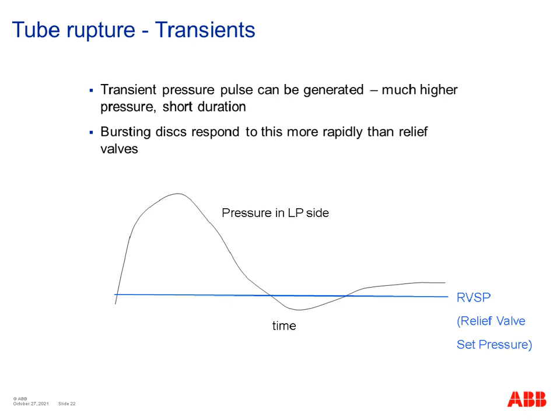So testing has shown that in the case of a sudden tube rupture, a shockwave can be set up in the heat exchanger as the HP fluid, which we're thinking of as a gas, compresses the liquid that's in the LP side as it comes through. So you have this shockwave that takes place in the event of the interstream leakage taking place. If the relief device on the LP side doesn't then open quickly enough to relieve the pressure, then the shockwave can bounce off something in the LP side of the exchanger, say a baffle plate or even the relief valve outlet line, and it can be reflected back into the exchanger again. So you get this reflection of the surge wave, and that adds another surge pressure again to what you've already got. And this is a short duration transient event, so it's all happening in milliseconds.